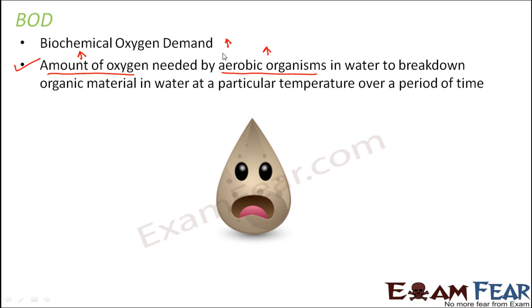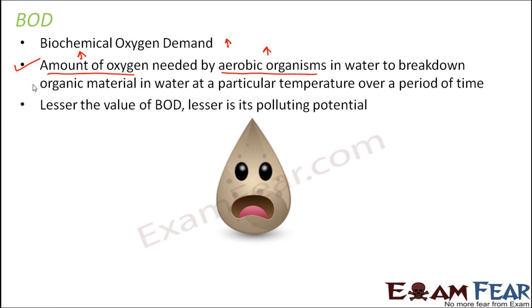When the value of BOD is more, the number of aerobic organisms is also more, and that happens when the amount of organic material is more. When organic material is more, the sewage is less treated and has more polluting potential. Our aim in sewage treatment is to reduce the polluting potential so the sewage becomes less harmful. There is a direct relationship: lesser the value of BOD, lesser is its polluting potential. We must ensure that BOD reduces to a very large extent, and that is where we stop the secondary treatment and say the sewage is properly treated.